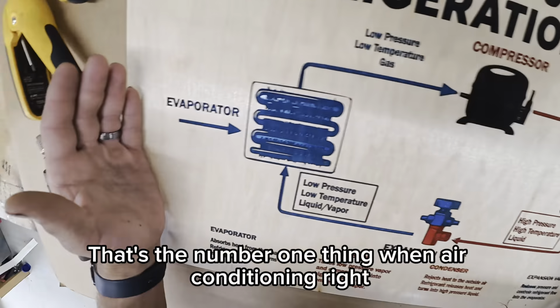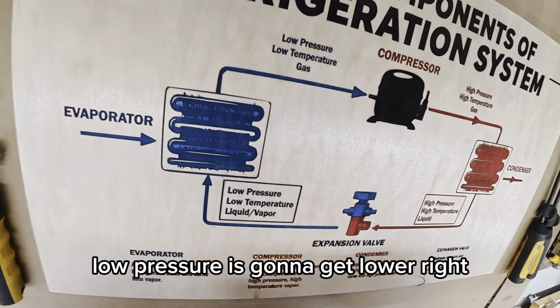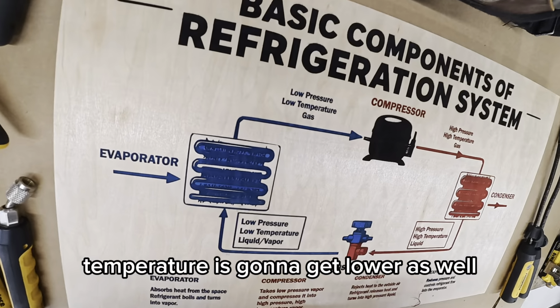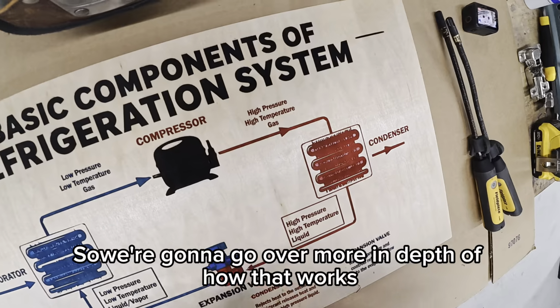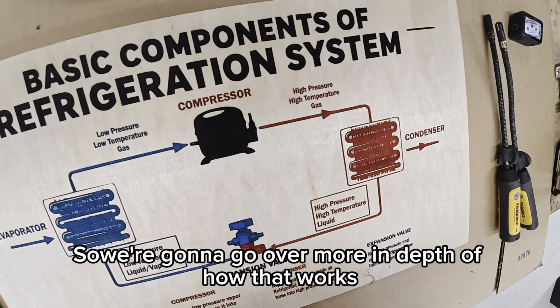Airflow before charge, right? So if our air's not moving outdoor or indoor, right? No air moving outdoor, high pressure is going to get even higher. If we're not moving any airflow indoor, low pressure is going to get lower, right? Temperature is going to get lower as well. So we're going to go over more in depth of how that works.